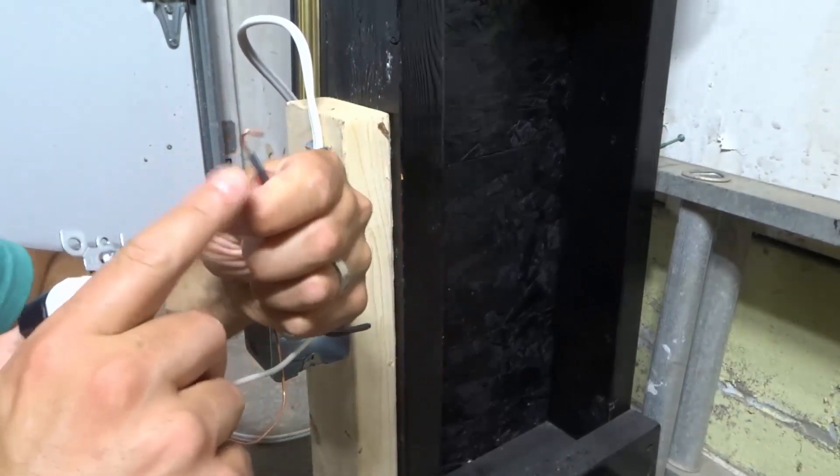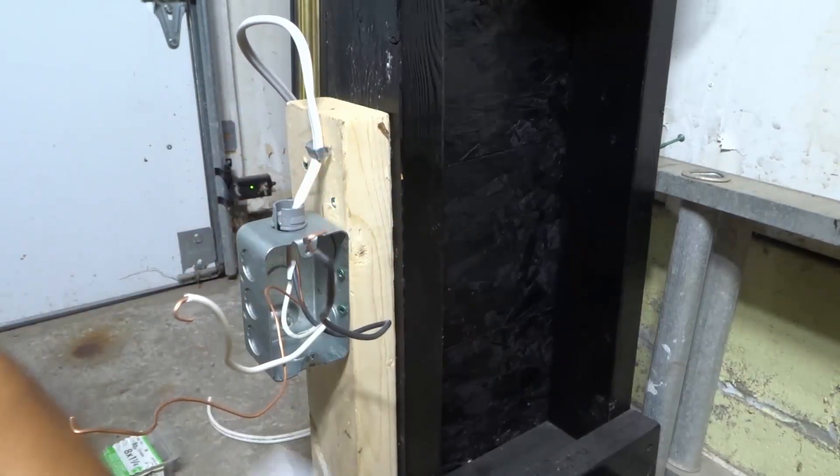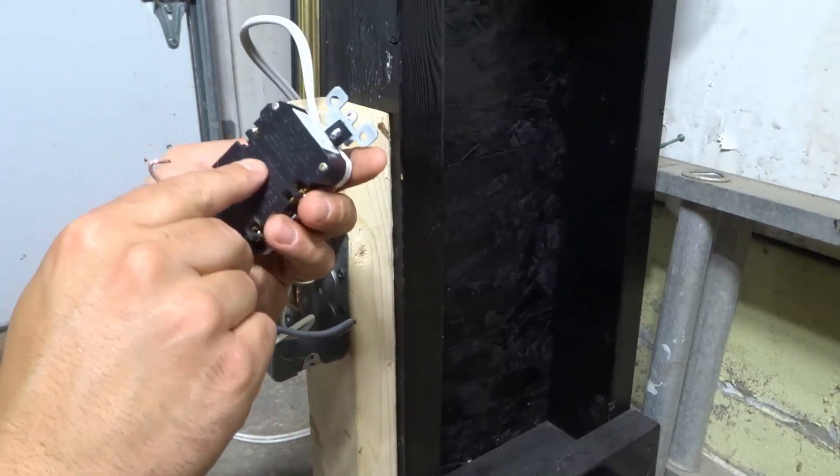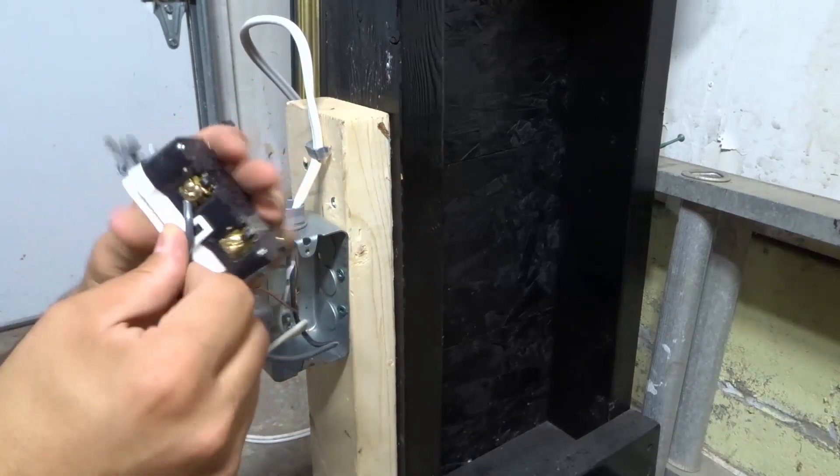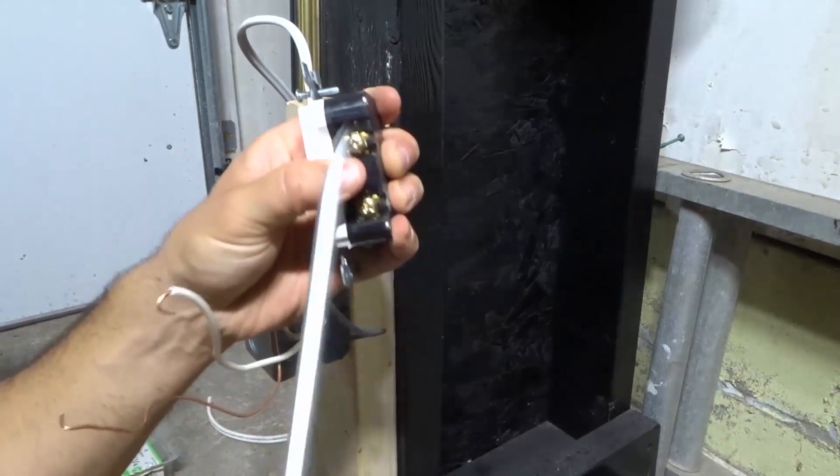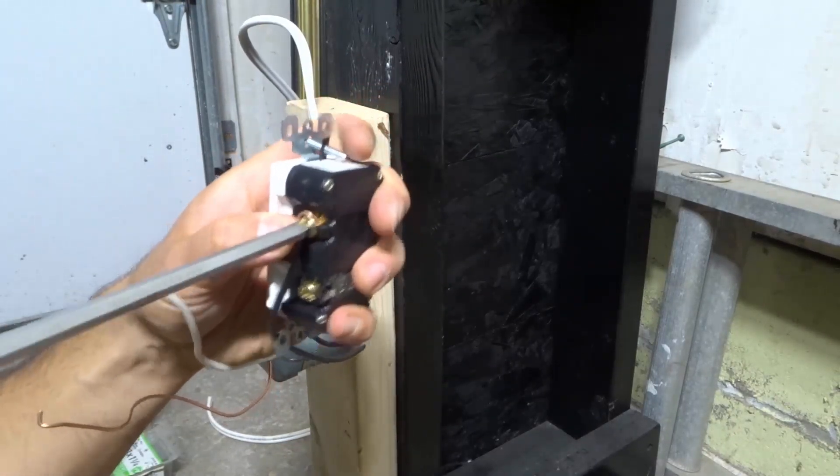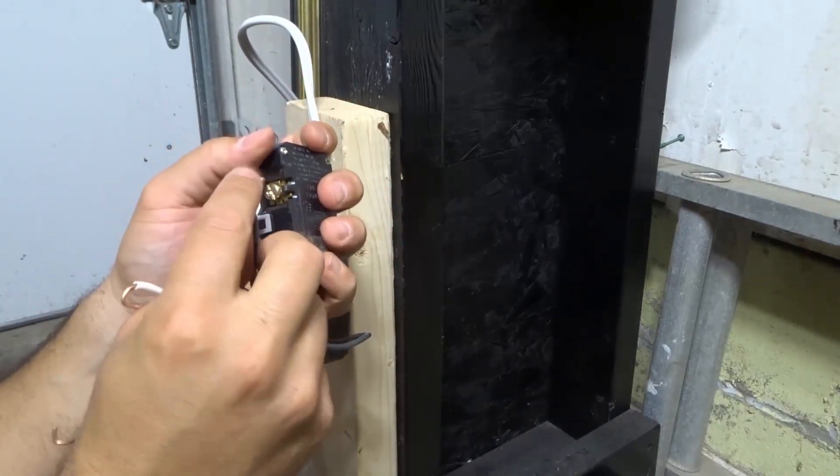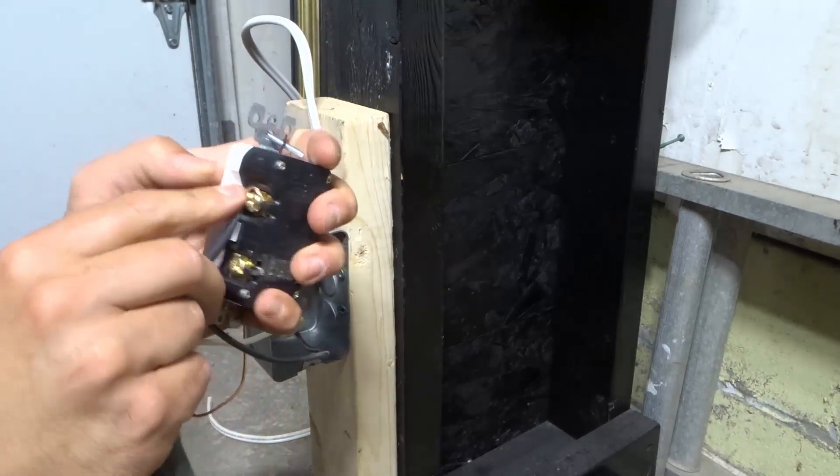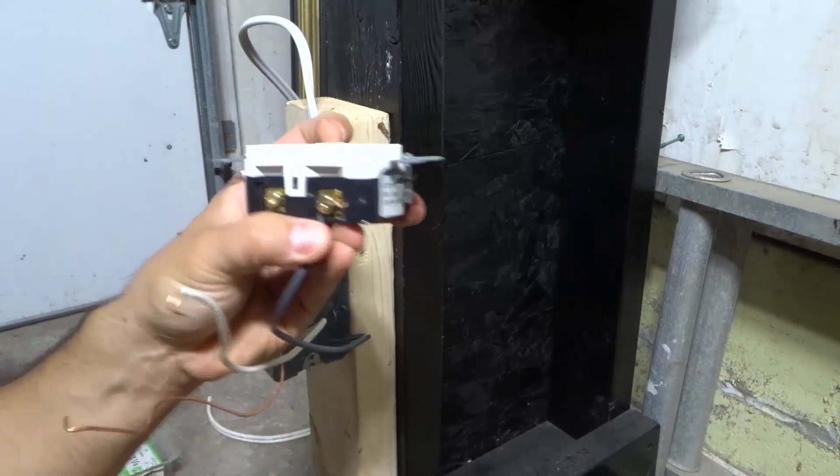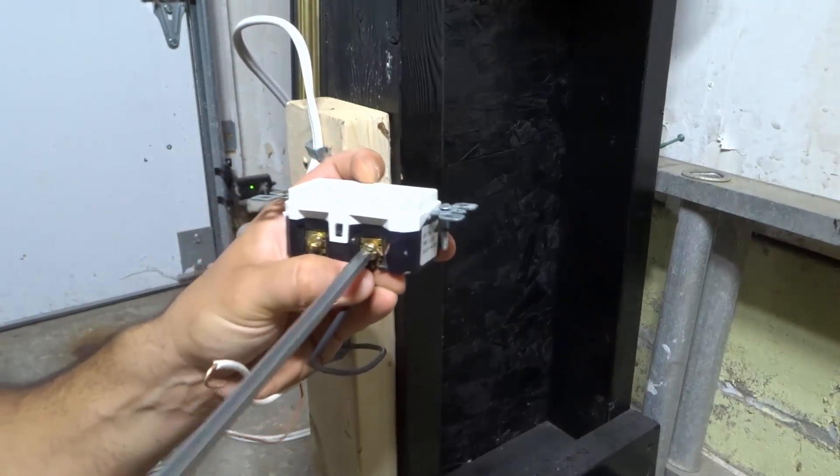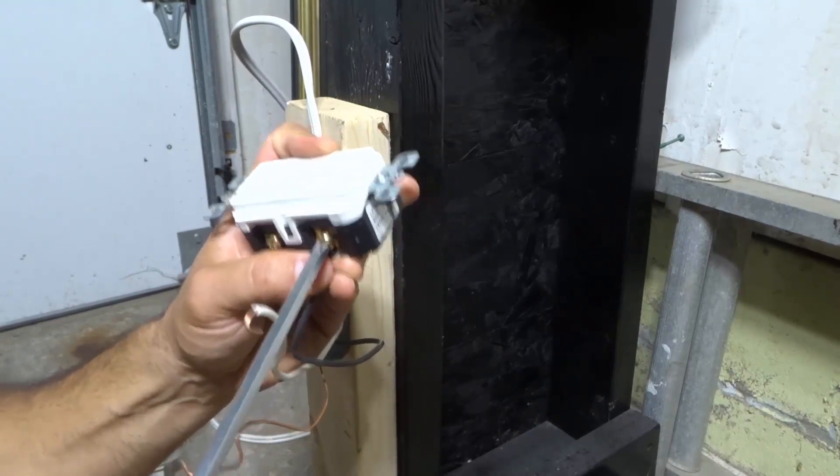What you're going to do is take your black wire and make sure your wires have a little loop on them. Take your black hot wire and place it on the hot side, on the line portion, which is the brass colored screw. Hook it around and tighten the screw down nicely. Make sure when you hook that wire around that the hook is traveling in the same direction as the tightening of the screw—in this case, clockwise. Tighten that screw down really tightly. Don't be afraid to be generous with your torque. We're connecting this on the line side because it's coming from the panel.